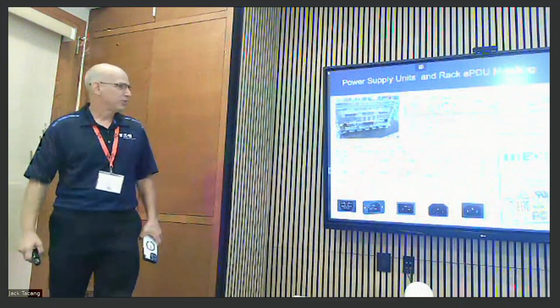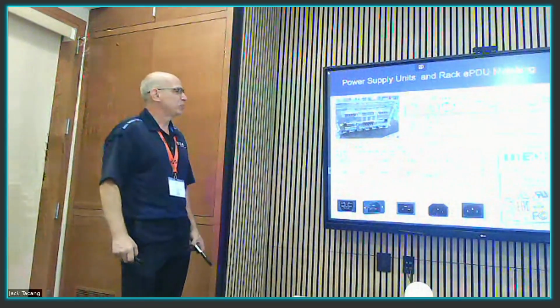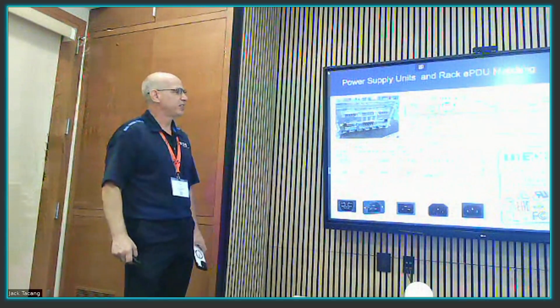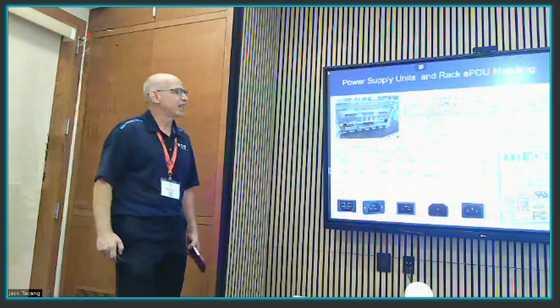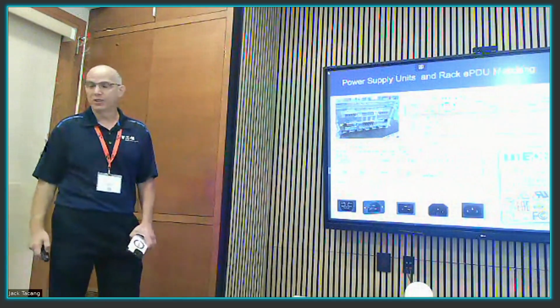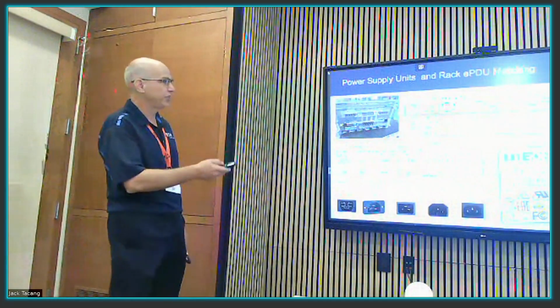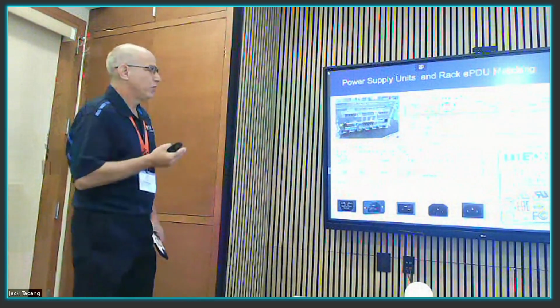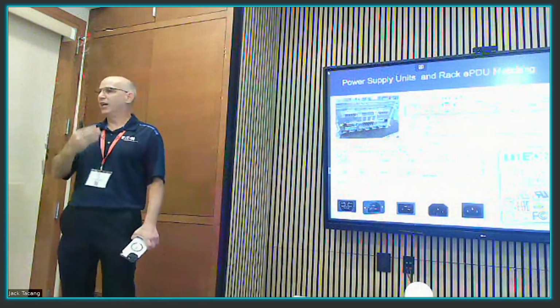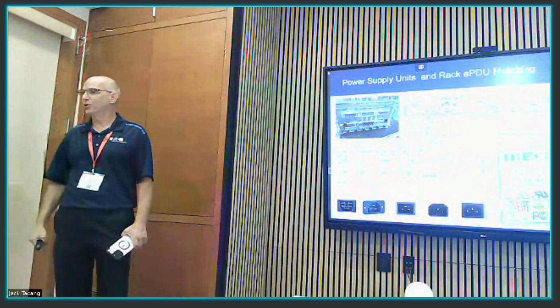It's an 80 Titanium Plus power supply, which means it has to be at least 94% efficient at full load. In this case, it's 95% efficient. So 5,200 watts is what it needs to drive to the equipment, but that's not the input source.